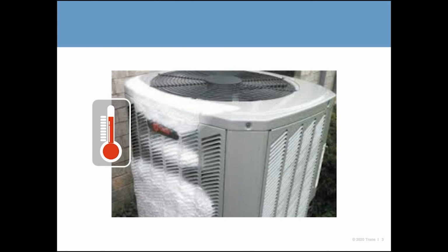All right, too much frost on that coil degrades performance, and you potentially get a lockout scenario, which you want to avoid. All right, so what we do is we reverse the cycle of the refrigeration circuit. We send hot refrigerant out to the coil, we melt the ice, and we go back into normal operation. All right, but there's a derate associated with that that needs to be known upfront for sizing.